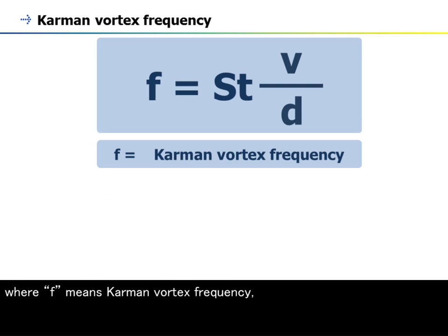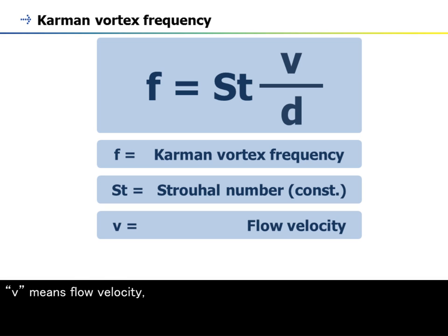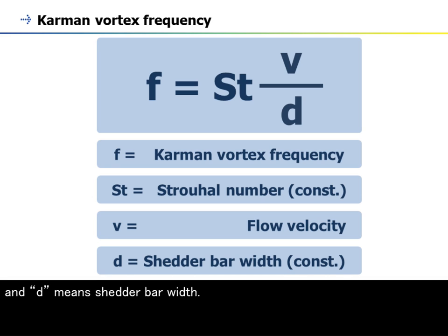Where f means Karman vortex frequency, St means Strouhal number, v means flow velocity, and d means shedder bar width.